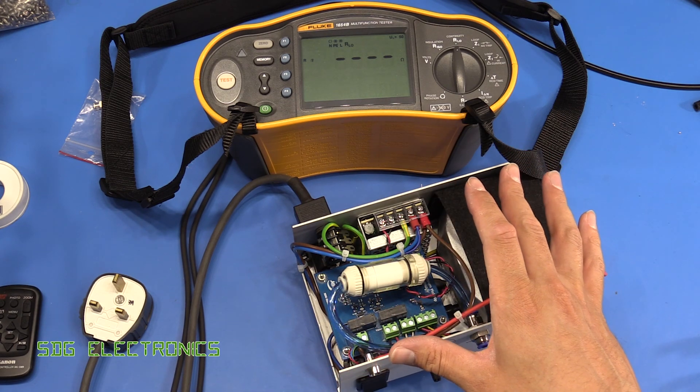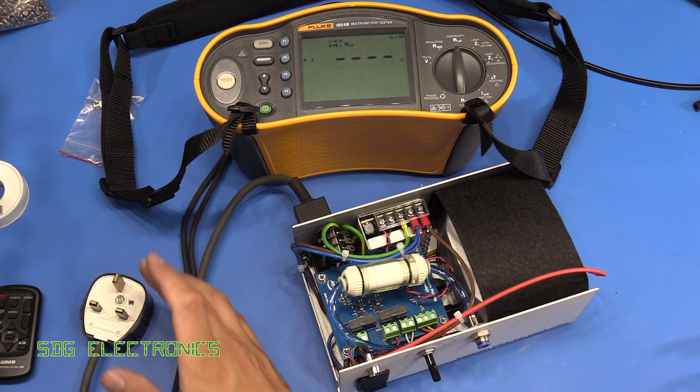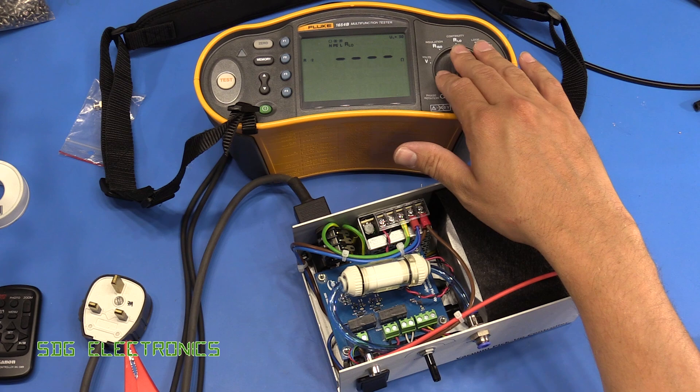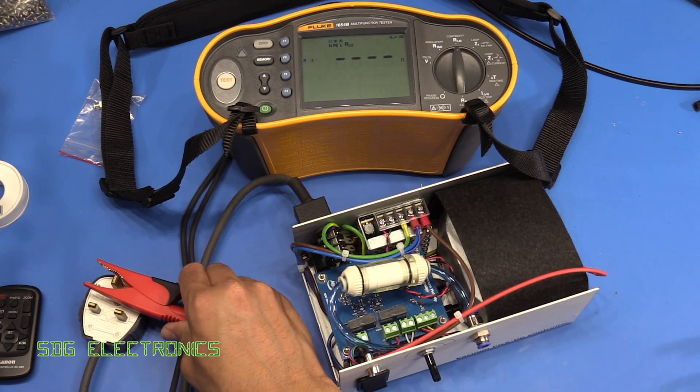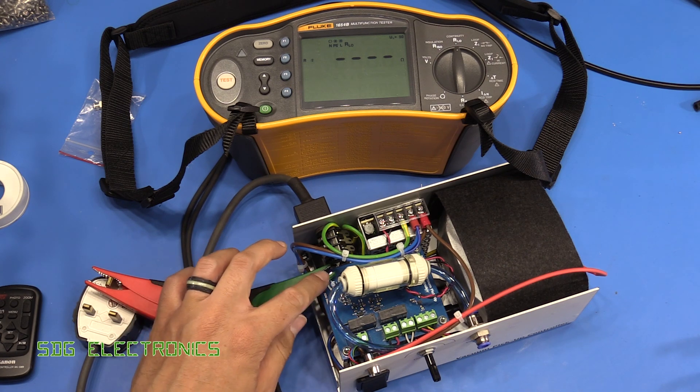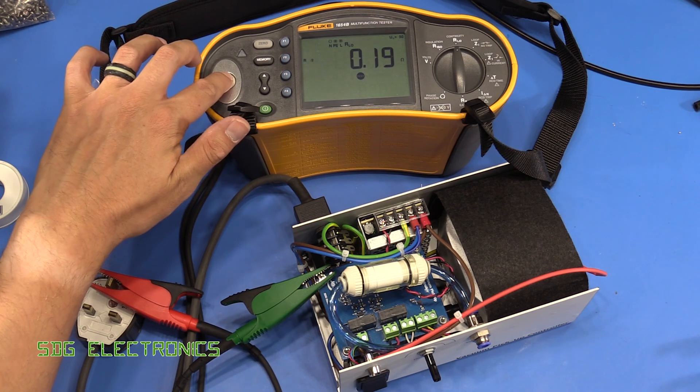Right, so just to make sure that this is safe, the first thing that we want to do is make sure that the chassis of the device is properly connected to the mains earth pin on the plug. So we've set the Fluke Multifunction Tester to continuity and we'll put one probe on the earth pin and one on the PCB mount because that's connected to the chassis. And there you go, you can see we get a reasonably low reading for continuity there.